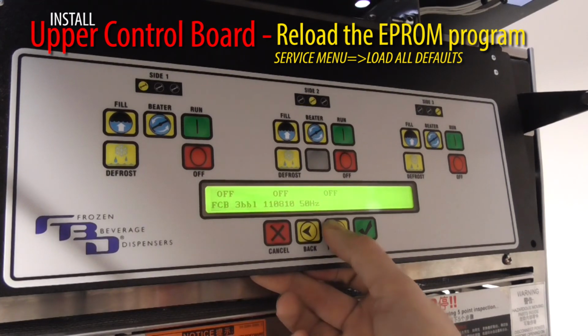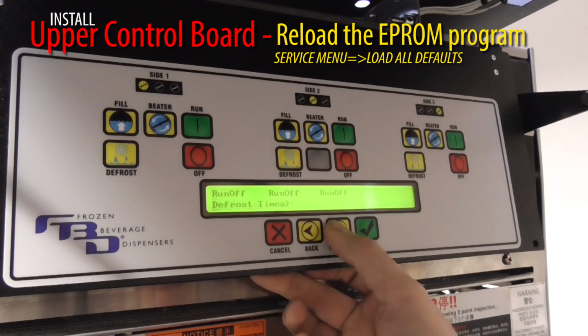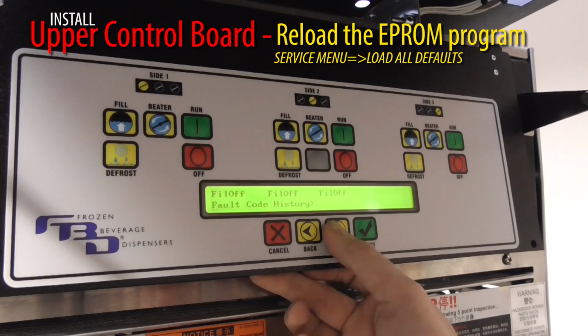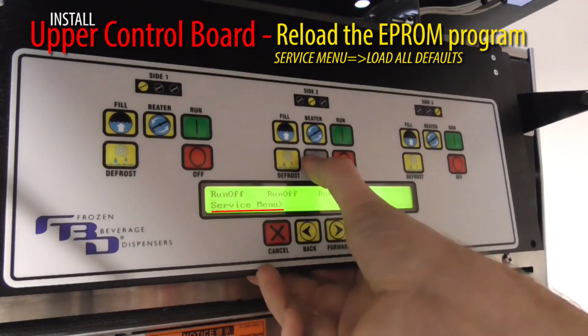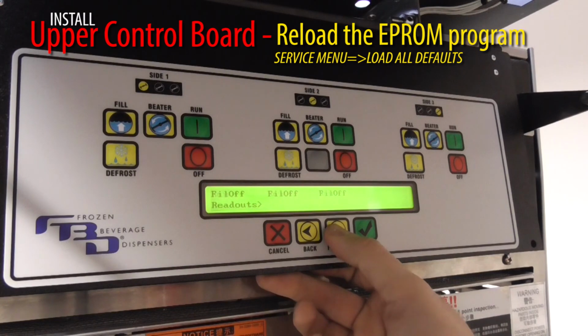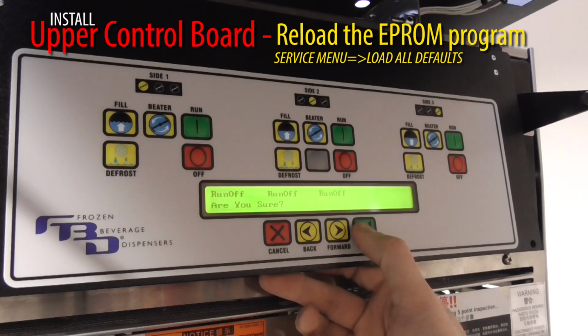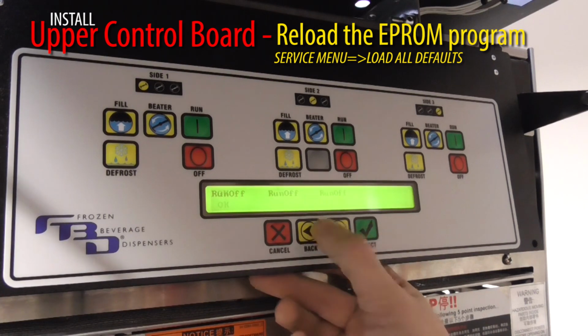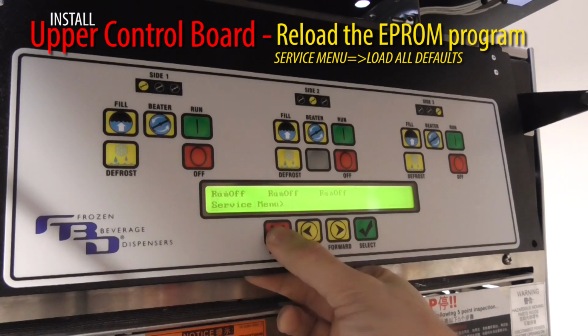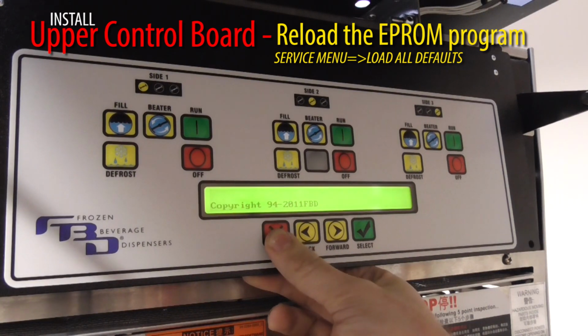scroll through to the service menu, which is accessed then by the grey button. At this level in the program menu, scroll through to load all defaults and press select. Press select again to confirm. Now we have pulled the program from the EEPROM into the memory. Then press cancel 4 times to get back to the default program position.